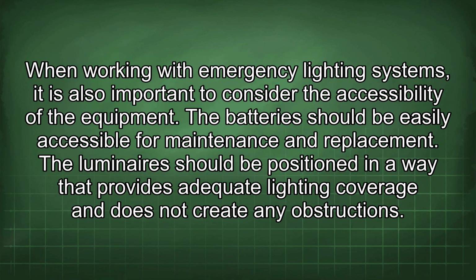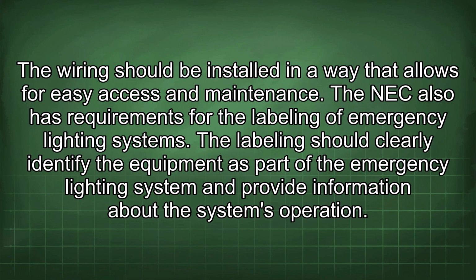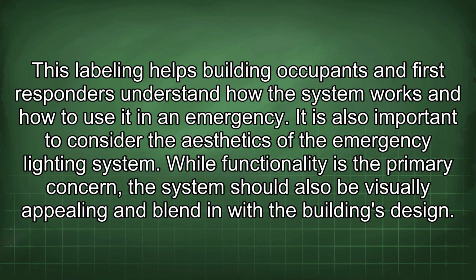When working with emergency lighting systems, it is also important to consider the accessibility of the equipment. The batteries should be easily accessible for maintenance and replacement. The luminaires should be positioned in a way that provides adequate lighting coverage and does not create any obstructions. The wiring should be installed in a way that allows for easy access and maintenance. The NEC also has requirements for the labeling of emergency lighting systems. The labeling should clearly identify the equipment as part of the emergency lighting system and provide information about the system's operation. This labeling helps building occupants and first responders understand how the system works and how to use it in an emergency.